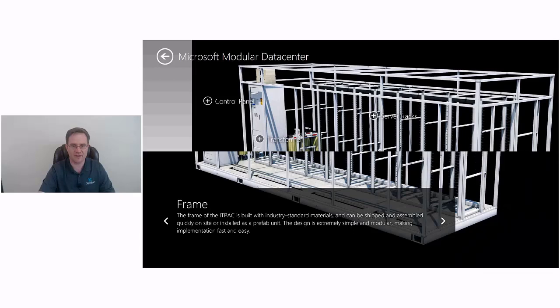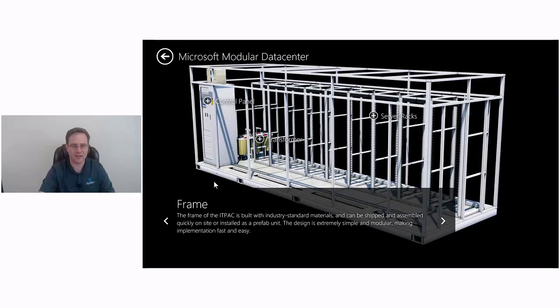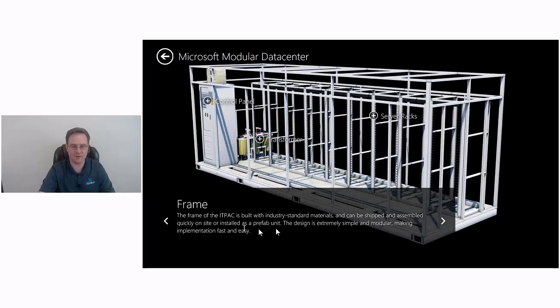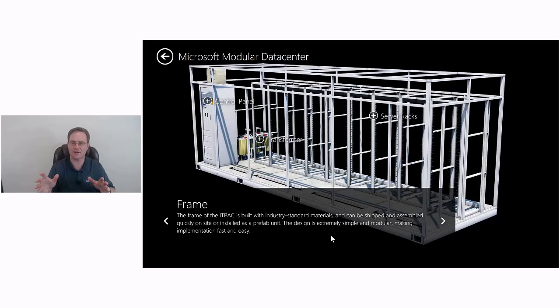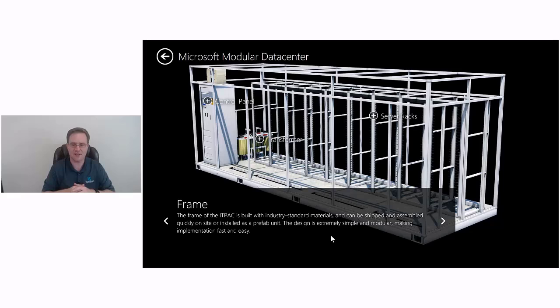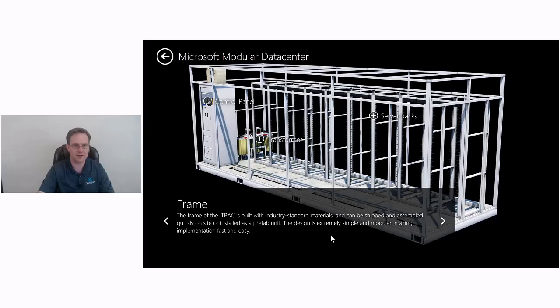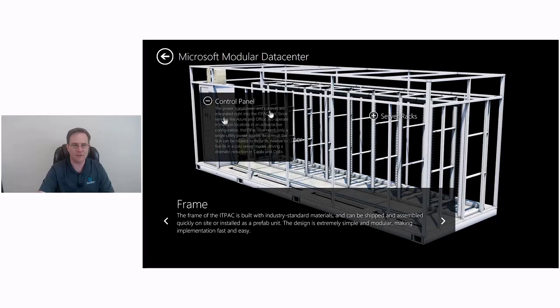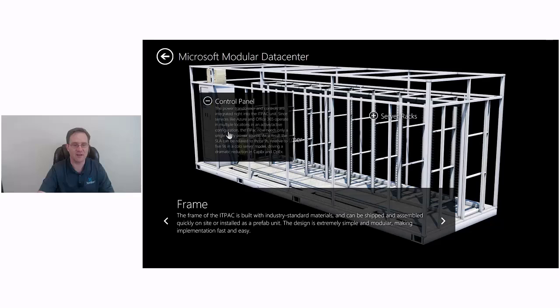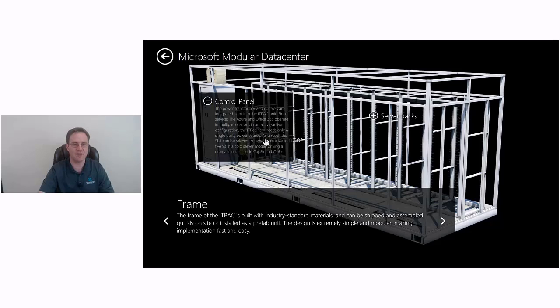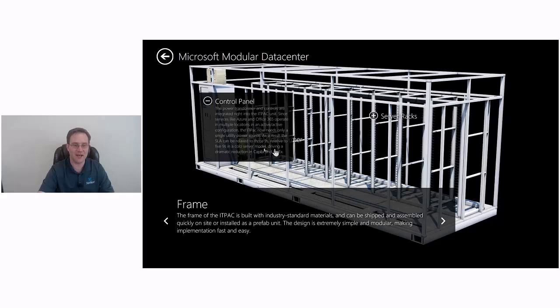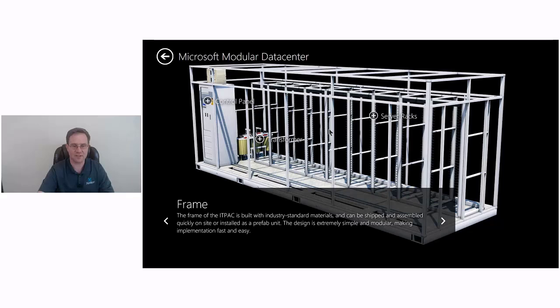The frame of the ITPAC is built with industry standard materials, can be shipped and assembled quickly on site or installed as a prefab unit. The design is extremely simple and modular, making implementation fast and easy. I've seen pictures of the Chicago Data Center where they can bring in these modular pieces and stack them up next to each other and add capacity. The control panel: the power transformer and controls are integrated right into the ITPAC unit. Since services like Azure and Office 365 operate in multiple locations in an active-active configuration, the ITPAC now needs only a single utility power source. As a result, the SLA can be relaxed to three nines relative to five nines in a colo server model, driving a dramatic reduction in CAPEX and OPEX.